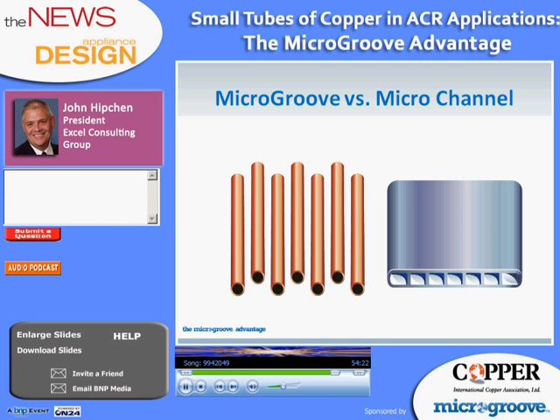And they published separate papers on tube circuitry and fin design. The tube circuitry research compared 7 millimeter tubes with smaller diameter 5 millimeter tubes. And although their simulations predicted higher refrigerant pressure drops for small diameter tubes, they found that by increasing the number of circuit branches and decreasing the single branch length, they also added more tubes in the circuit design, the refrigerant pressure drop could be kept within reasonable levels, and they could do that at a significant savings in tube materials.